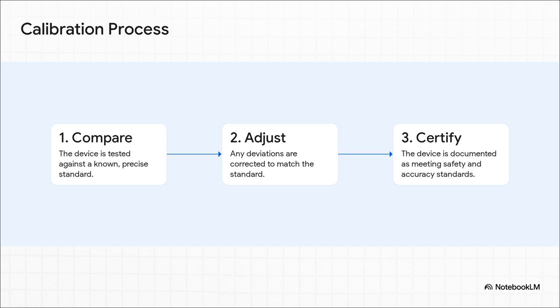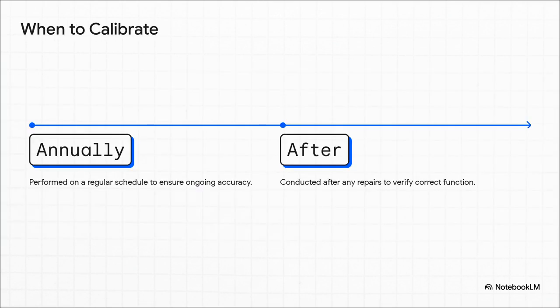The device gets a sticker, a seal of approval that says, yep, this has been checked and it's ready for patient care. And you know, this isn't a one-and-done kind of deal. Precision needs constant vigilance. At the very least, most critical equipment is calibrated every single year. But just as important, any time a device is repaired or serviced, it has to be recalibrated right then and there. Why? Because you've got to make sure the repair itself didn't knock its accuracy out of whack. It's this constant cycle of verification.